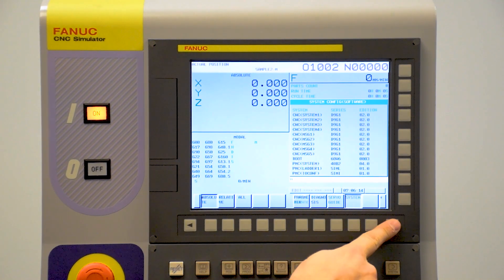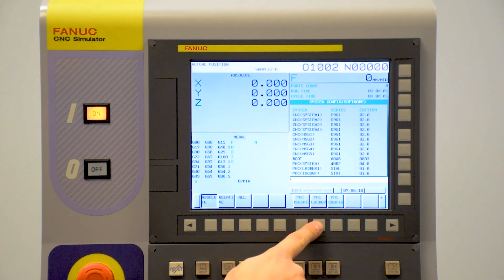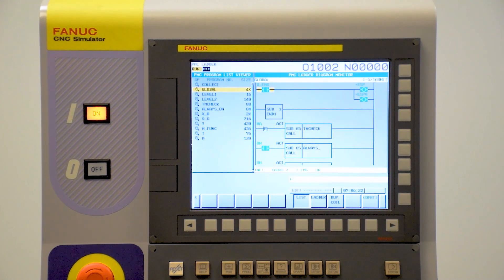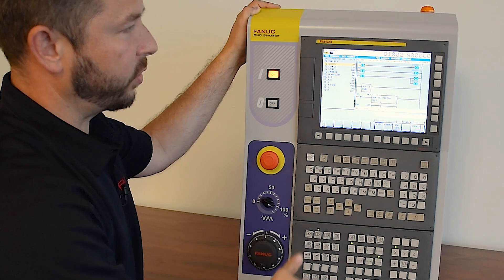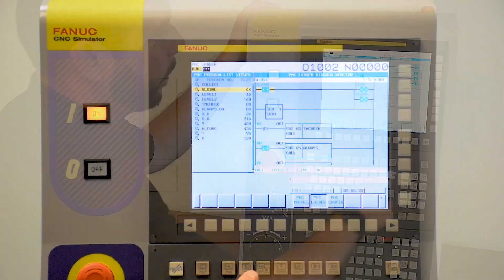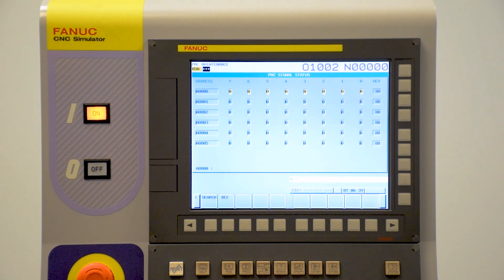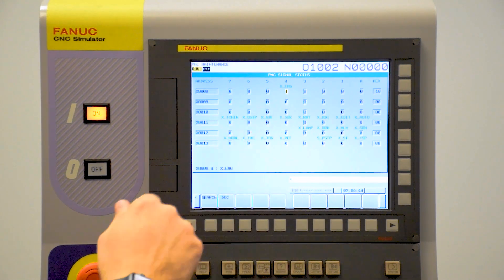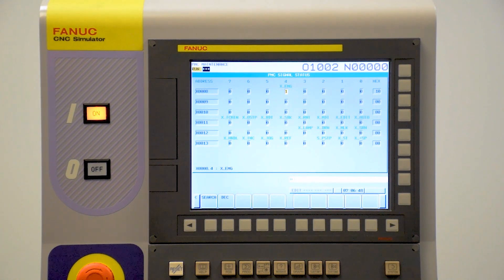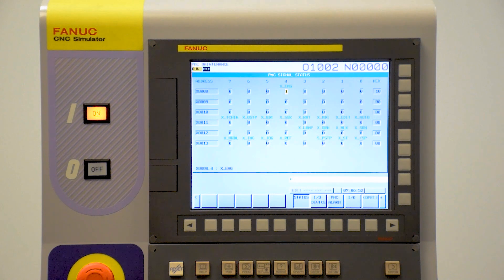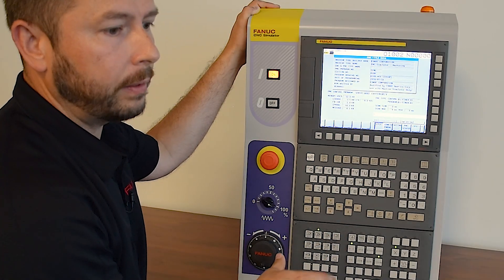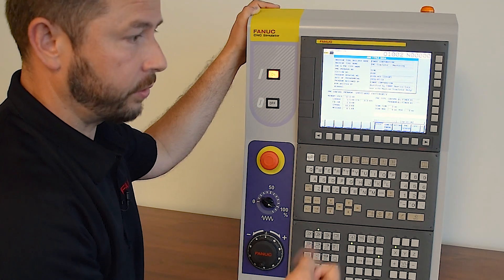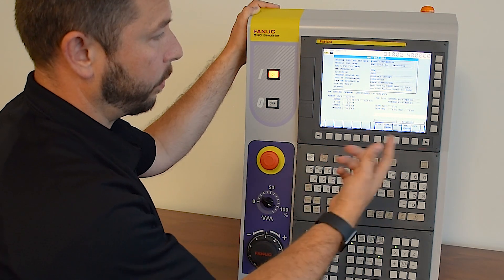As we go across on the soft keys, we get to our PMC screens. Those of you familiar with PLC programming logic will find this looks very similar — a series of inputs and coils for outputs. There's a lot of interaction between the PMC and the CNC, so instead of just X and Y addresses, we have F and G addresses as well. On the maintenance screen we can look at specific inputs; X8-bit 4 is usually the emergency stop and we can see the bit triggering. The PMC — programmable machine control — is live and active inside the control. The config will tell you the version of the ladder, and you can edit the ladder using the CD that comes with the unit, which includes a sample lathe program and a sample mill program.